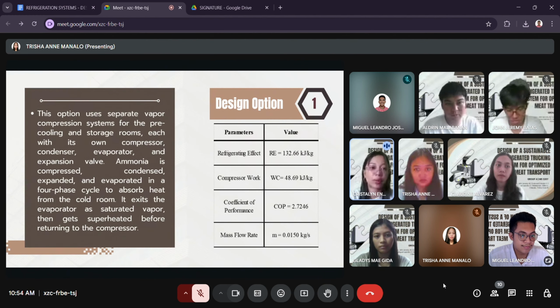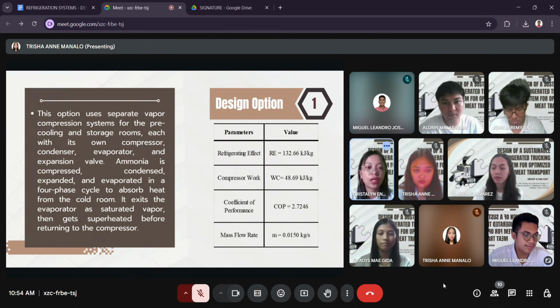This option uses a separate vapor compression system for the pre-cooling and storage room, each with its own compressor, condenser, evaporator, and expansion valve. Ammonia is compressed, condensed, expanded, and evaporated in a four-phase cycle to absorb heat from the cold room. It exits the evaporator as saturated vapor, then gets superheated before returning to the compressor.